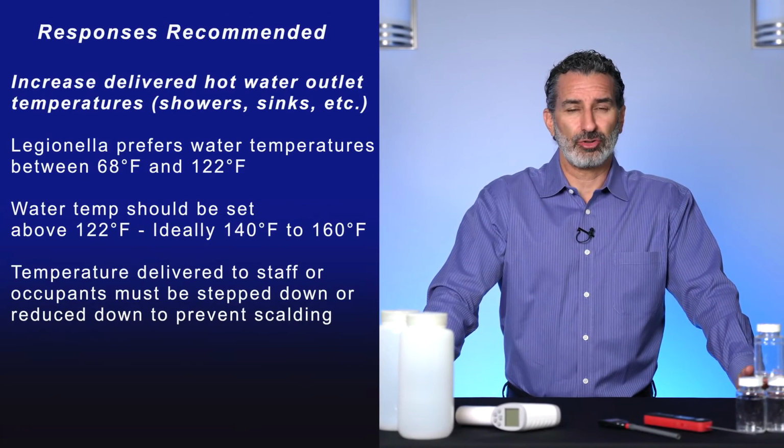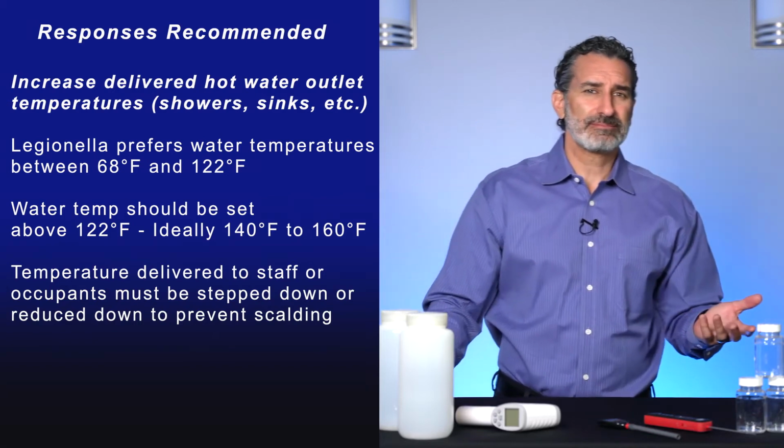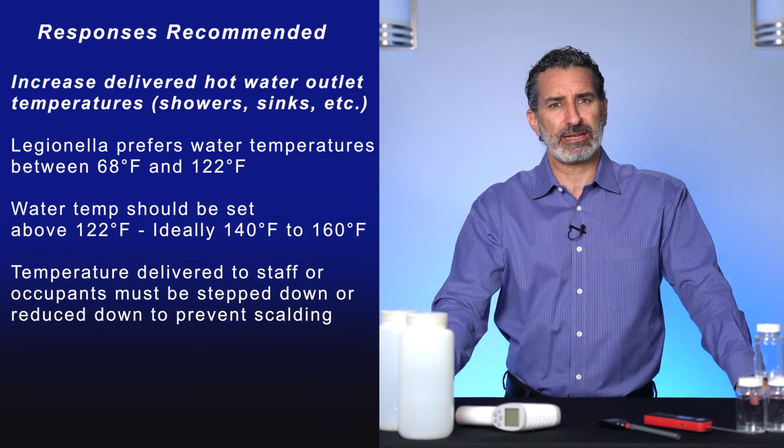Controlling Legionella means controlling your water temperatures. The water temperatures that Legionella likes are the same things that you and I like. Not too hot and not too cold. Approximately 68 degrees to 122 degrees Fahrenheit.